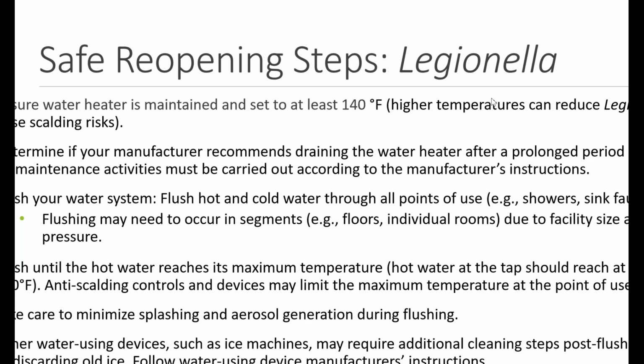If this is a school or somewhere where you need to really control what temperature the water's coming out, because you don't want any scald or burn risk, that maximum temperature might be limited at the point of use. So maybe you need to use a different system in addition to just heating the water to help take care of the bacteria.